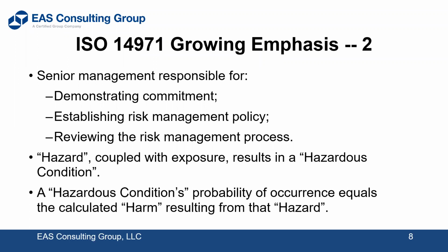for pharmaceuticals. And you notice here, the last two bullet points talk about a hazard coupled with the exposure to that hazard by the individual resulting in a hazardous situation or condition. And for that hazardous situation or condition, the probability of occurrence equals the calculated harm resulting from that hazard. Now, as we go through this, you'll notice that in times past, we used to calculate a risk priority number: severity times probability times control, or effectiveness of control to prevent that fault from occurring in the manufacturing process. But now probability and control have been combined under probability. So although you'll see some references to control in our discussion here, ultimately that has to be folded into probability. So you're basically dealing with severity times probability to consider the overall risk of your product.